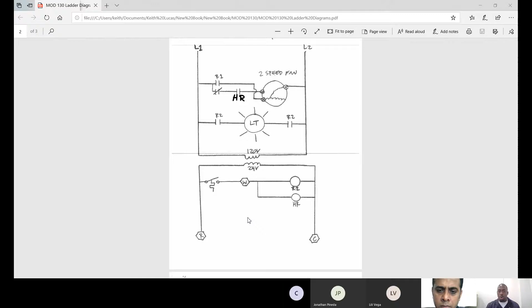Well, there are two fan controls. There's the low speed, which is controlled by the heat relay, and by terminal number 2 on relay 1. And then there's the high speed, which is connected to G and is operated either by the fan, if you just switch the fan on, or if you turn the AC on, which is illustrated right here. So that's our diagram.